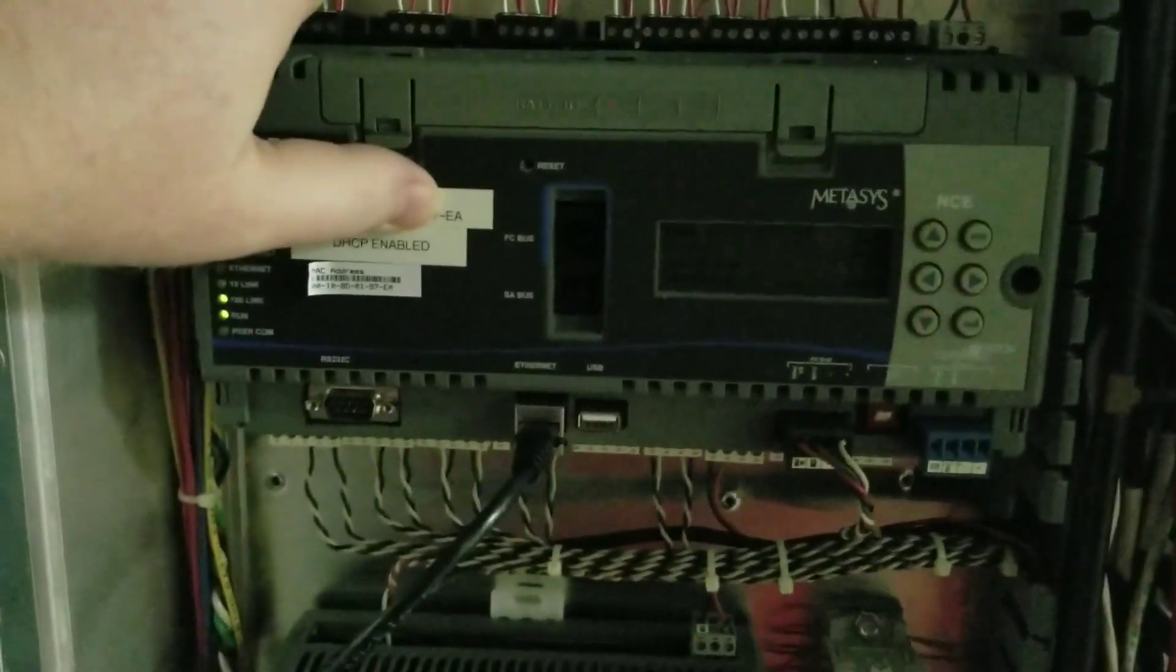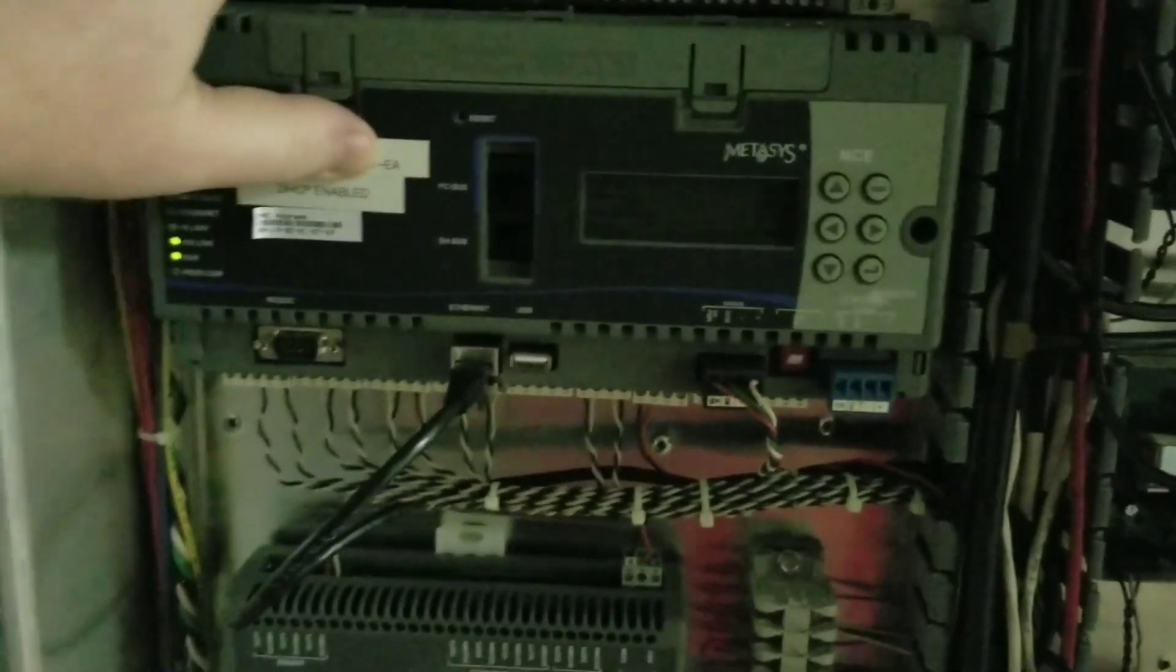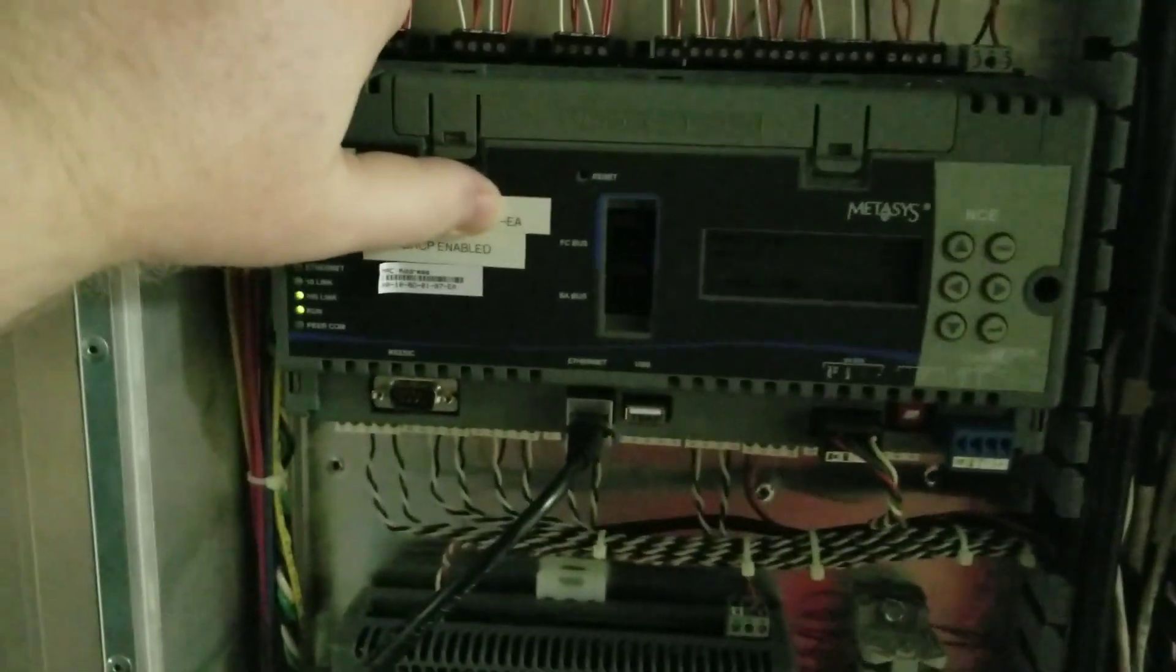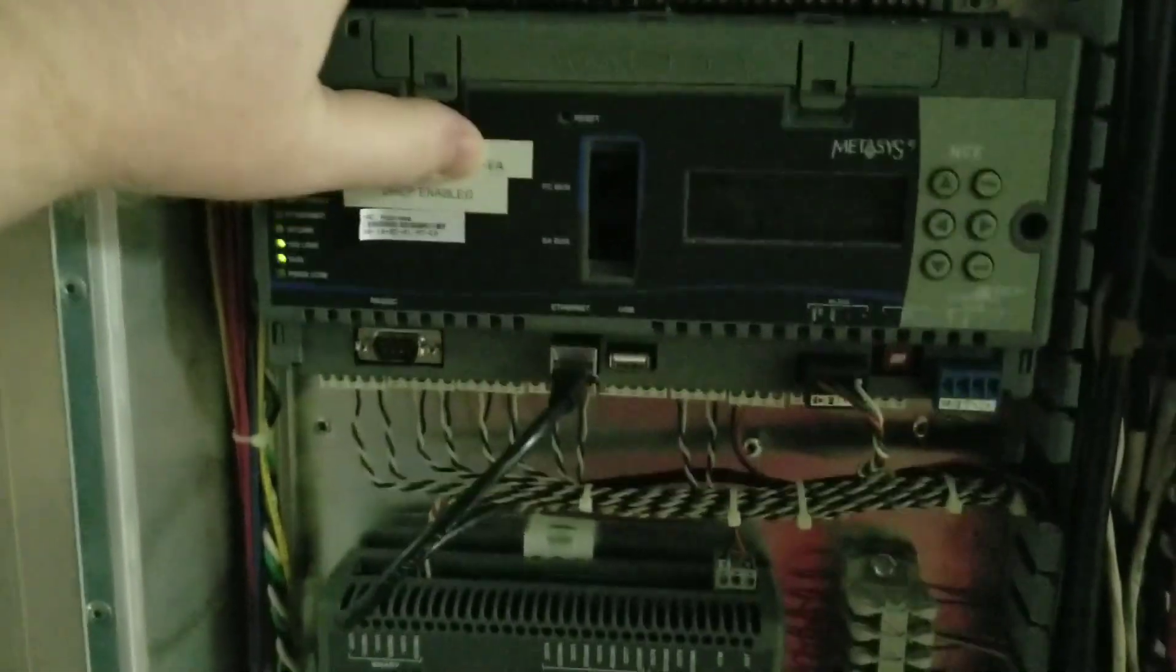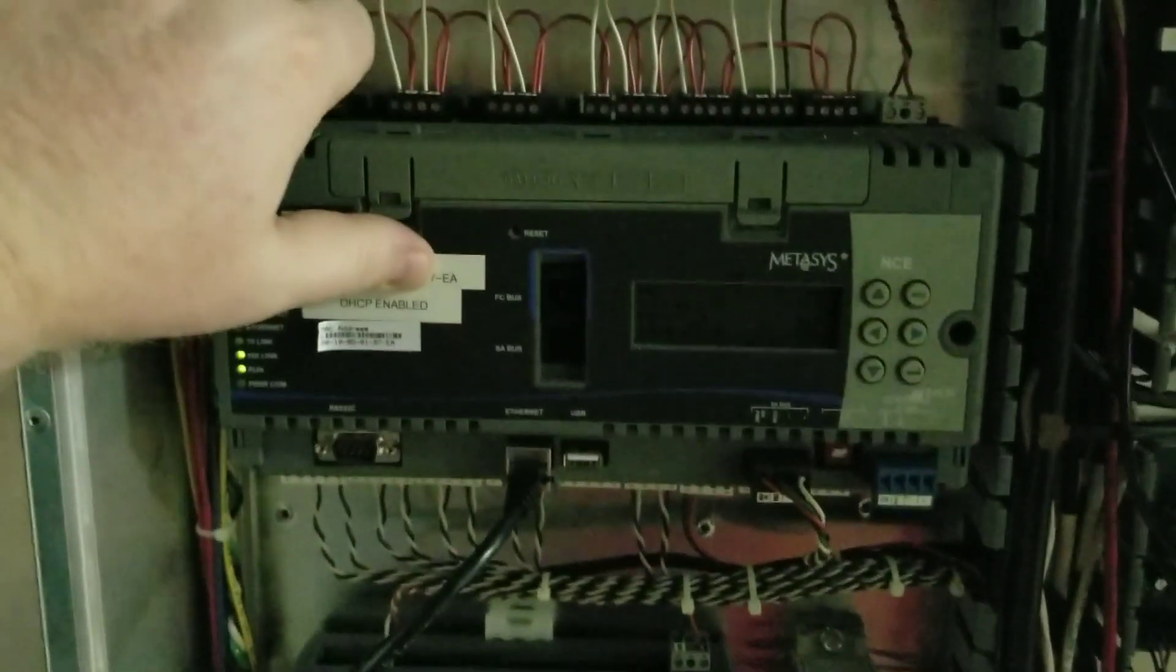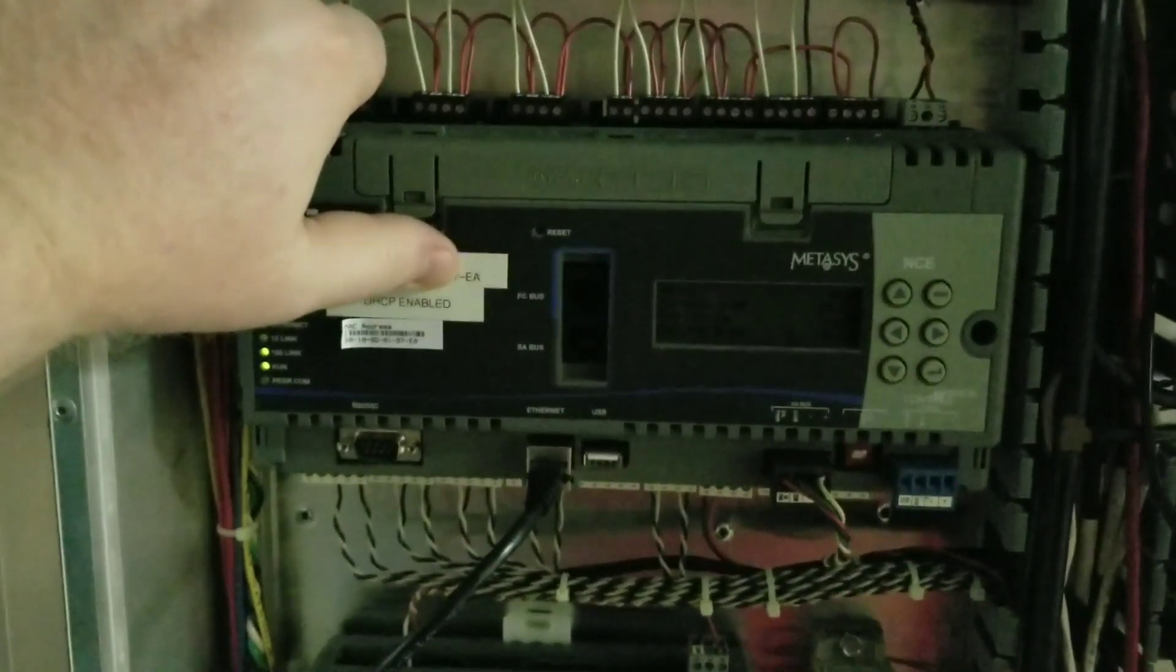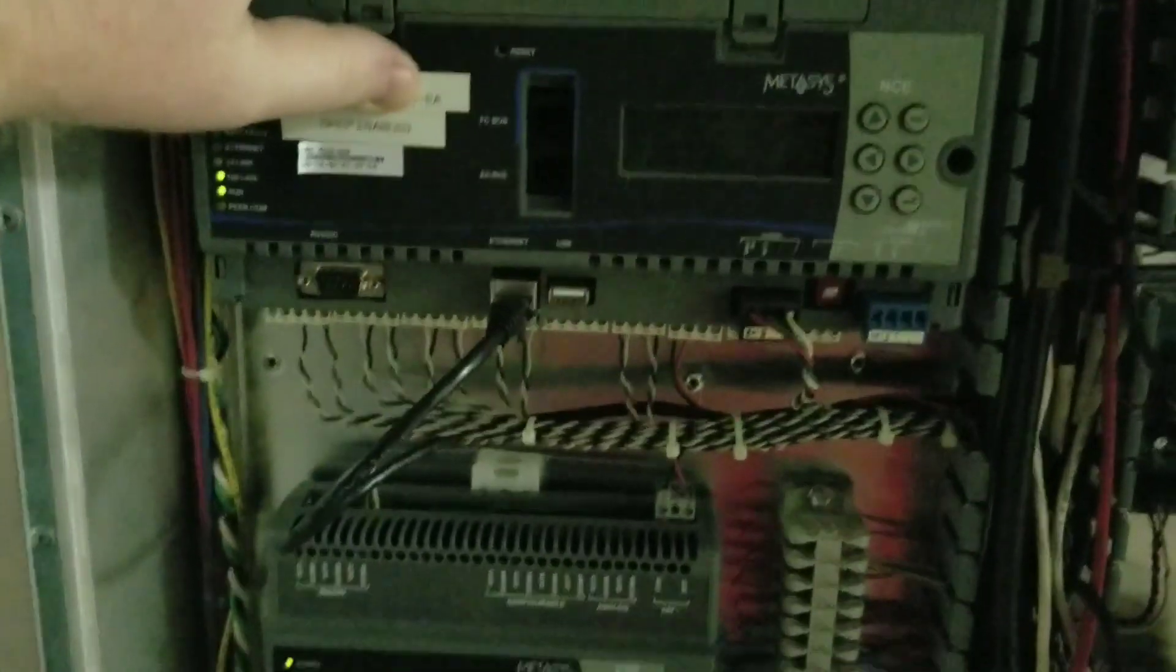Guys, what we're going to be doing in this video is I'm going to be showing you how to use the Metasys imaging tool, the Johnson Controls imaging tool, to re-image an NCE or an NAE.